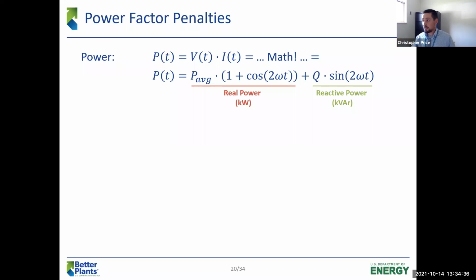The other part is reactive power, measured in kilovolt amperes reactive. This is necessary to operate your equipment, but it does no actual work. For example, in a motor, for the motor to operate, there need to be magnetic fields set up in the motor. Those magnetic fields don't do work, but they allow the motor to spin. So you need both of these components.